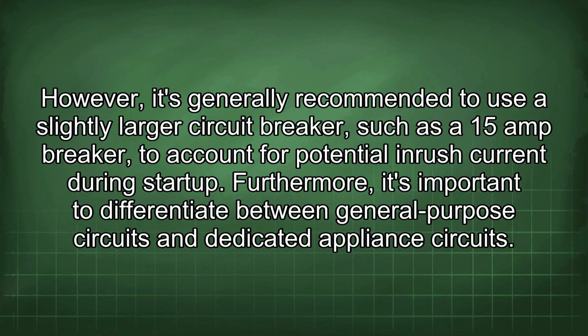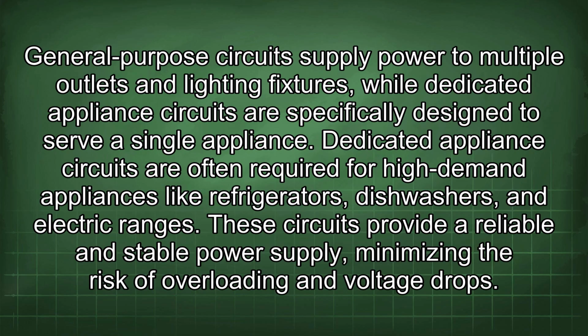However, it's generally recommended to use a slightly larger circuit breaker, such as a 15-amp breaker, to account for potential inrush current during startup. Furthermore, it's important to differentiate between general-purpose circuits and dedicated appliance circuits. General-purpose circuits supply power to multiple outlets and lighting fixtures, while dedicated appliance circuits are specifically designed to serve a single appliance. Dedicated appliance circuits are often required for high-demand appliances like refrigerators, dishwashers, and electric ranges. These circuits provide a reliable and stable power supply, minimizing the risk of overloading and voltage drops.